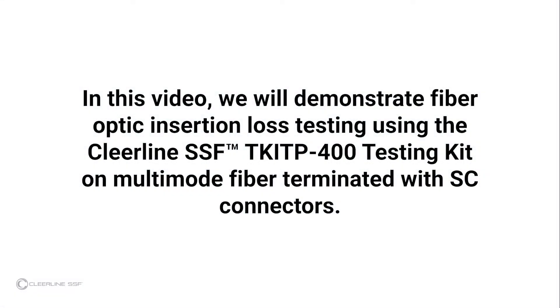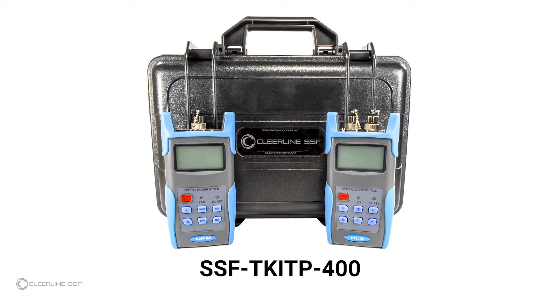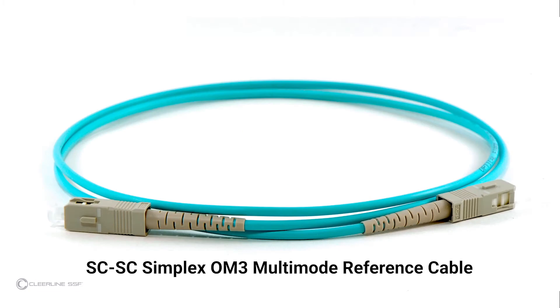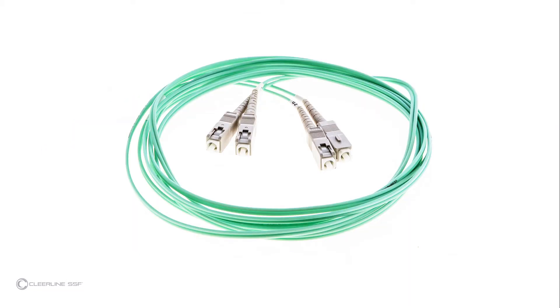In this video, we will demonstrate fiber optic insertion loss testing using the Cleerline SSF TKITP-400 testing kit on multimode fiber terminated with SC connectors. Required materials are the SSF-TKITP-400 kit with included light source and power meter, an SC-to-SC feed-through adapter, and one simplex SC-to-SC multimode reference cable for single cable reference testing, plus the cable under test.